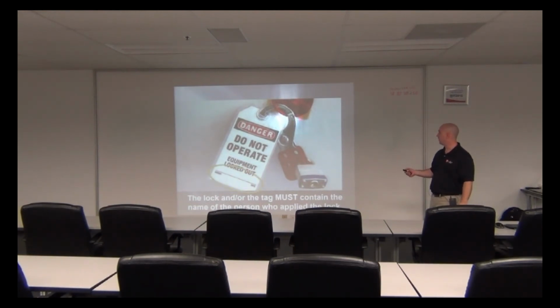I don't mind using these as lockout points. I don't know if you guys have that kind of a disconnect on any of your panels, but they can break a lot, they're pretty bad about that. So I always say you need a backup plan on them because you don't know if they function correctly, and I've been in a lot of places that have those. Or it could be a handle type on the door with an on and off, but it's way over here, and I just touch it a little bit, and it moves freely, then I get somebody to come over and they just spin it. It doesn't do anything, and it happens all the time. It's so crazy that could even be the situation, and that's our lockout point.